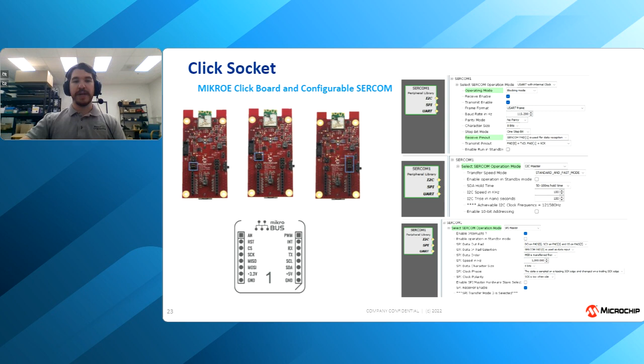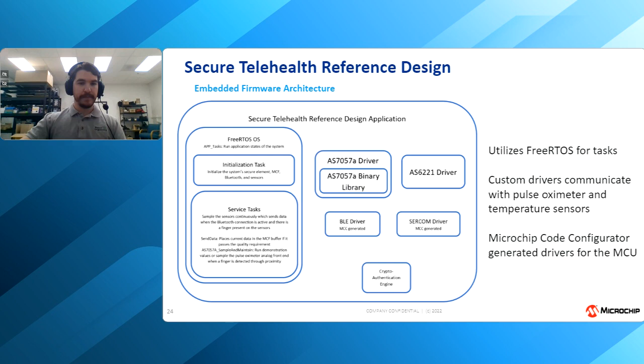So now taking a look at the firmware side of things, you can see here on the left a block diagram of the main application that is running on this board. It utilizes FreeRTOS for some initialization tasks and then service tasks. The service tasks connect to 2 custom drivers built specifically for communicating with the temperature sensor and pulse oximeter front end for this board. And then we have additional Bluetooth and the serial communication drivers that are built by the Microchip code configurator in that IDE, specifically for the WBZ350, which is very beneficial for quick prototyping and changing things around. Currently, the second SERCOM connected to the Click board is configured as a UART port to be able to get some debugging information out, which is a nice beneficial addition to have.